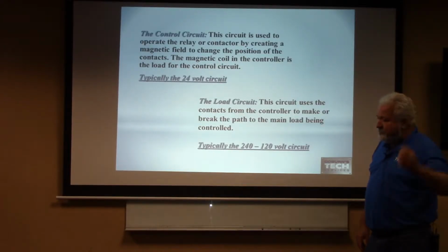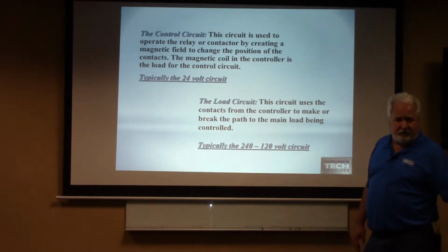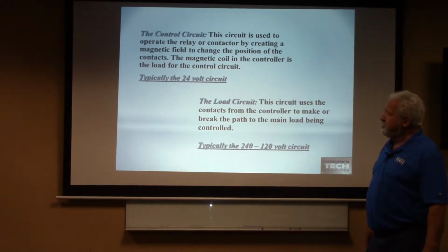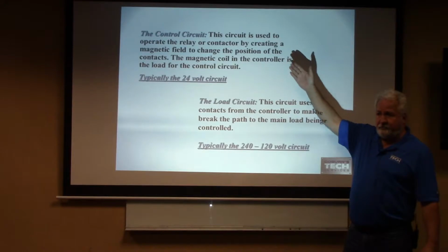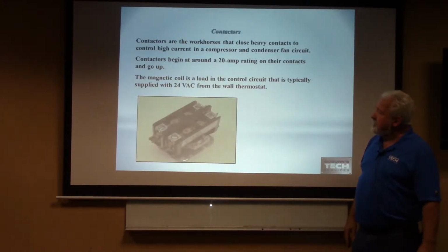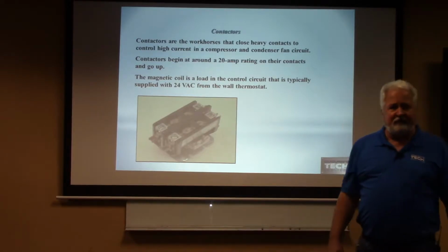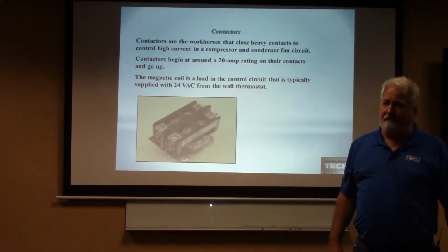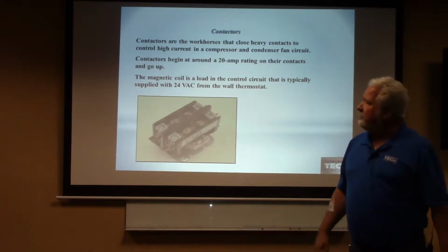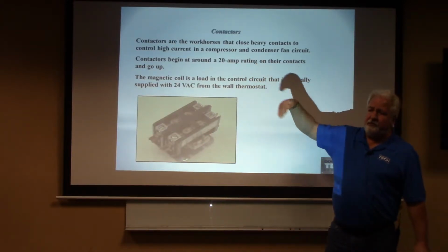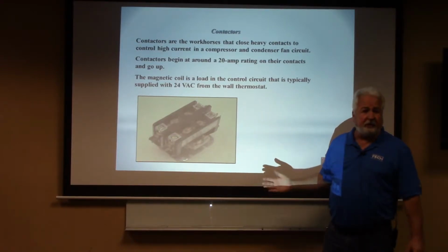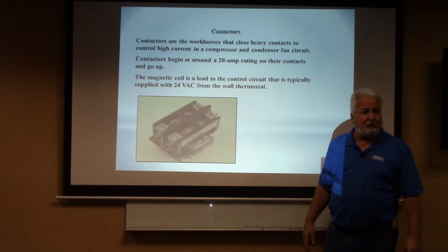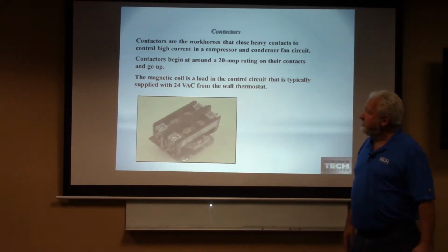Typically the control circuit is what we call our 24 volt circuit. That's going to be our thermostat and anything that's in that circuit. The load circuit is typically going to be our high voltage, 120 or 240 volt side of that circuit. So our control circuit controls the loads, is that right? Good. So on this contactor, what's the difference between a contactor and a fan relay? Both of them have a magnet, both of them have contacts. All of that stuff is typically the same, but it's usually right around 20 amps where they make the difference. If it goes above 20 amps, it becomes a contactor. Below 20 amps, it's a relay. Don't know why, but that's where the breakover is. So just a little piece of information for you to understand.